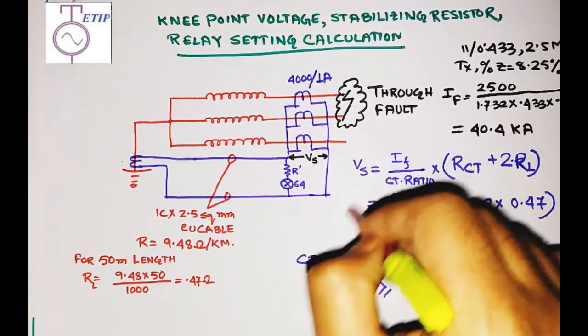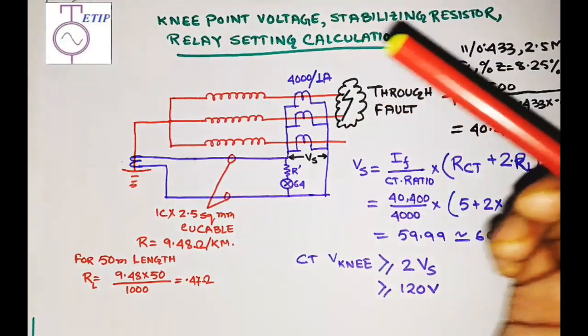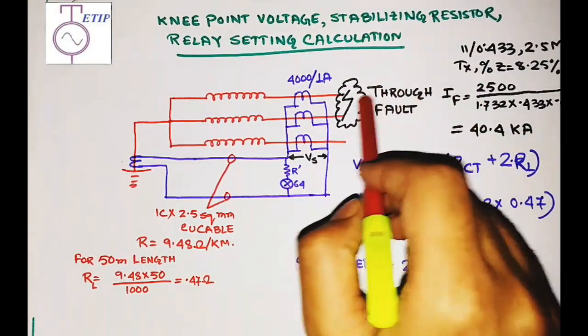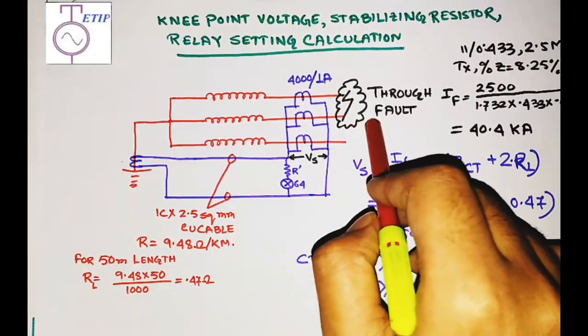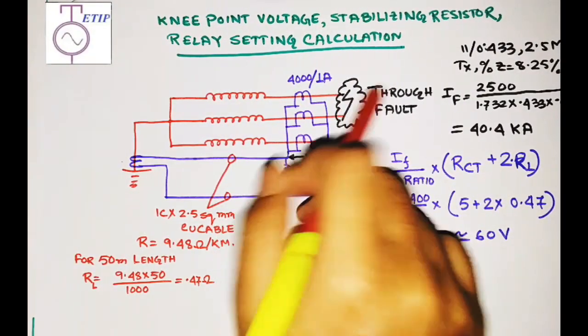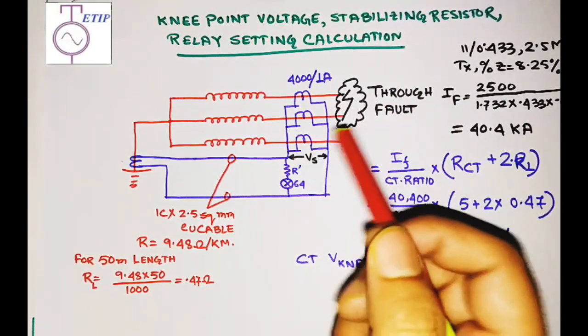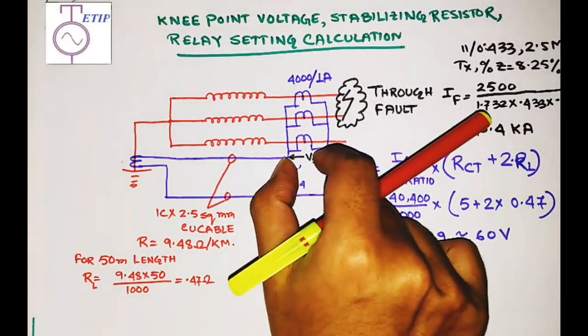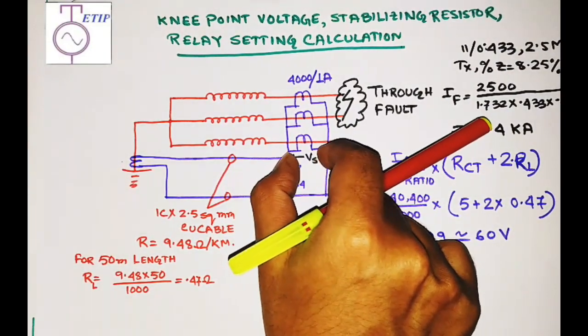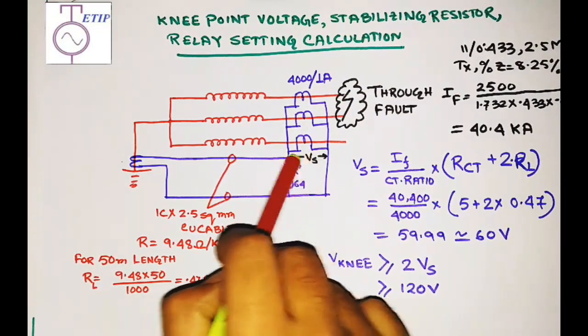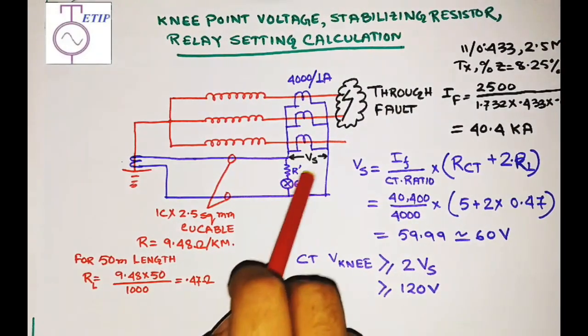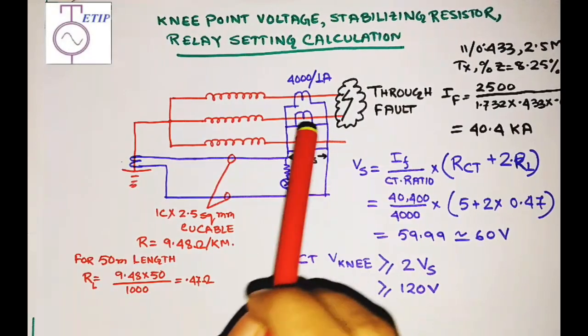But what if there is a through fault or phase fault outside the restricted earth fault zone? Suppose there is a line-to-line fault or three-phase fault — then a huge current will flow through these CTs. When the huge current flows through the CT, the CT gets saturated, and due to saturation a voltage appears across these CTs.